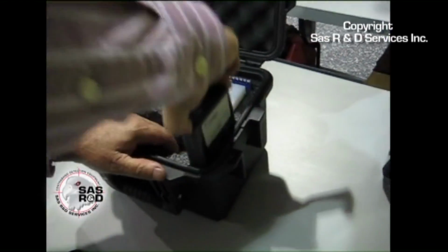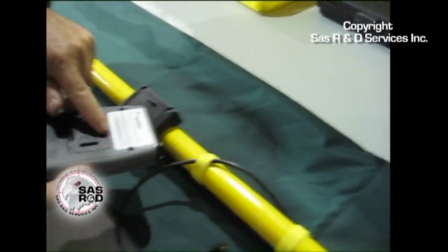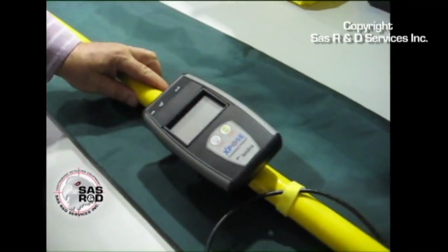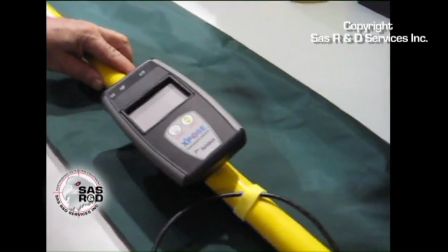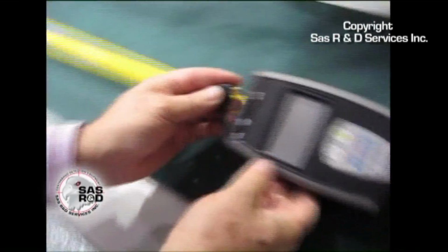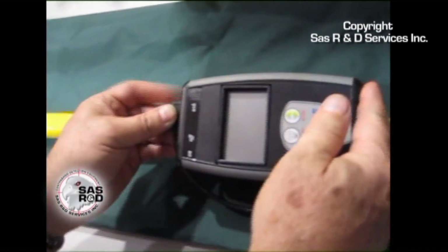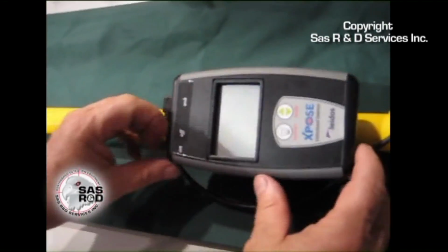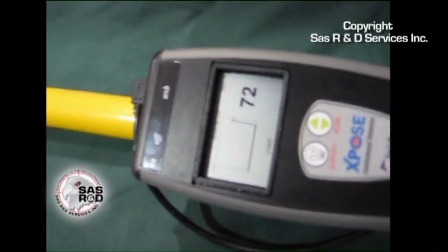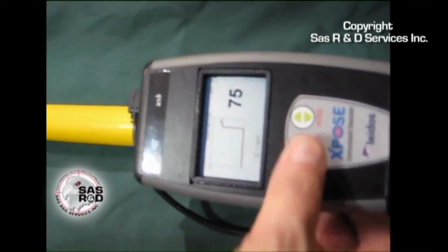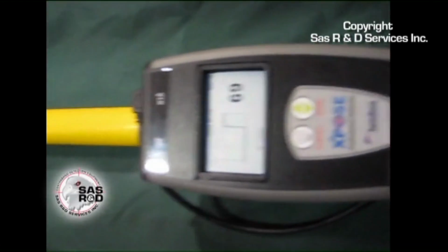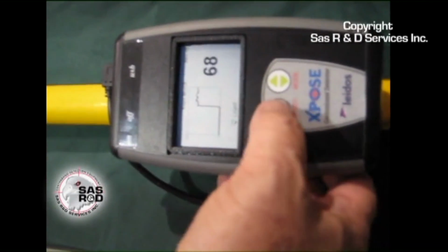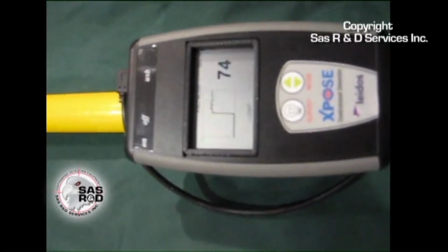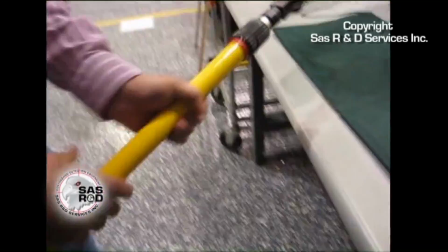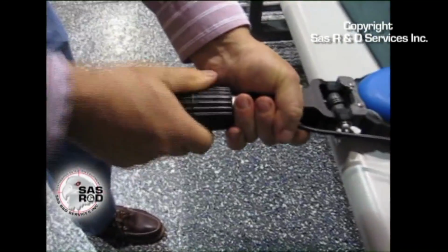Next, remove the display from the molded carry case. The remote display has a magnet to hold it into the extender pole, so just line it up and attach it to the pole. Then take the USB cord on the other end of the extender pole and attach it to the remote display. Turn the remote unit on and you will see numbers starting to register. To turn on the backlight, simply press the light icon, then you will push it in again to turn off the backlight. The backlight feature operates in the same manner on the Xpose unit. Remember to turn off the backlight when not in use to save the battery life of the Xpose and the Xpose remote. The unit is now ready to be used for density detection.